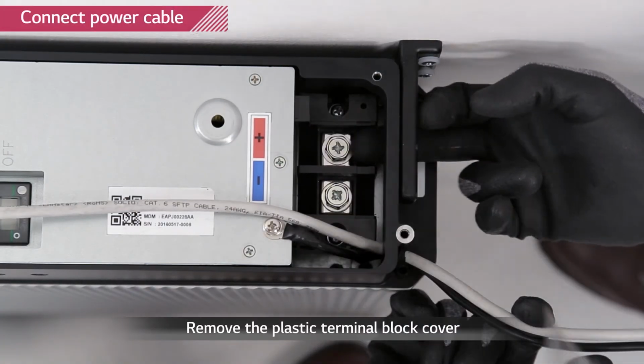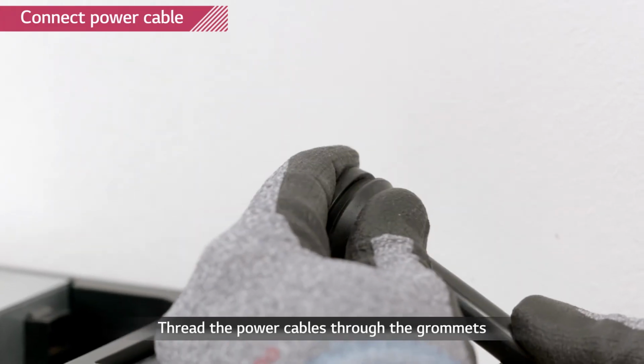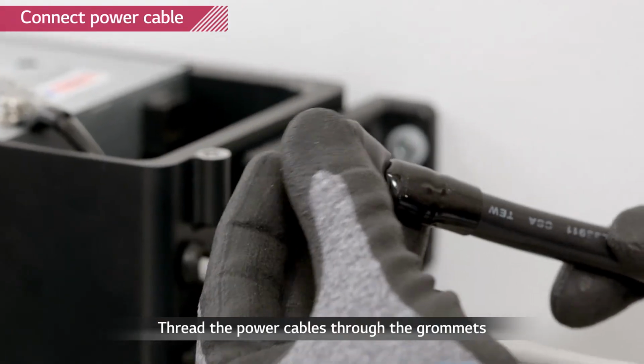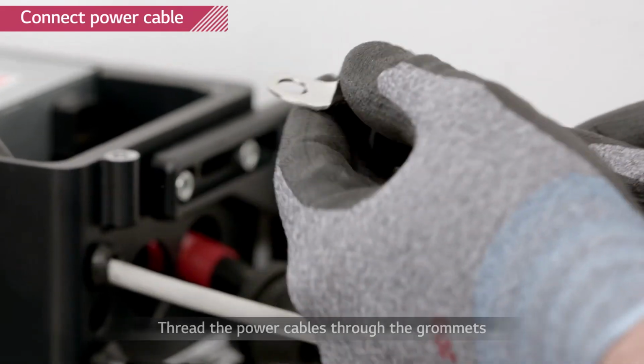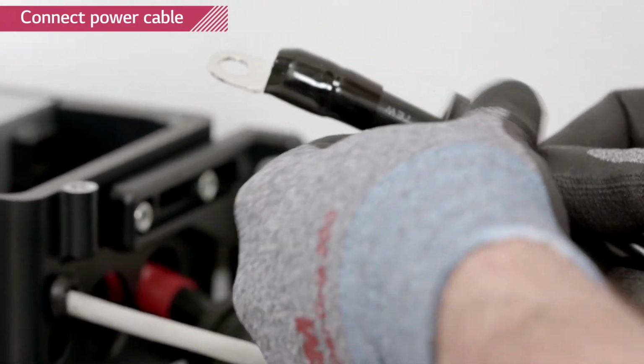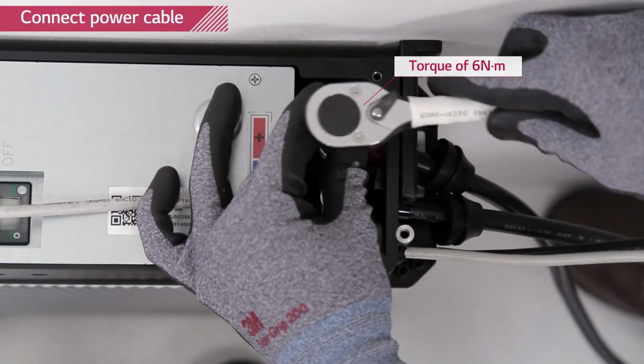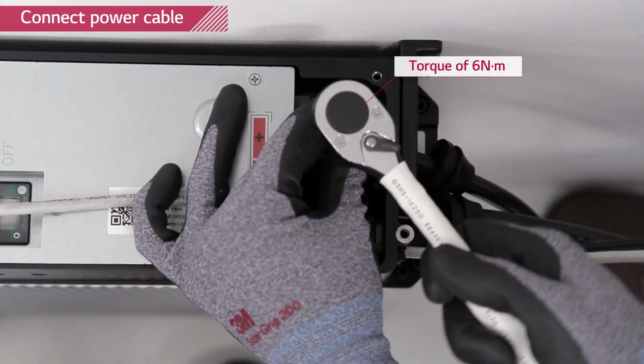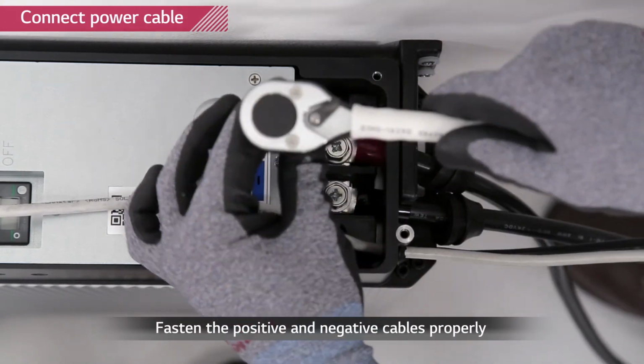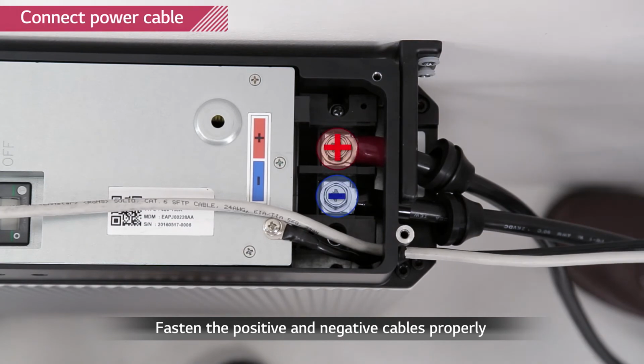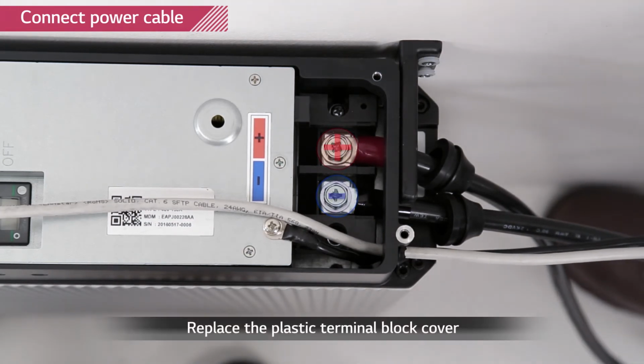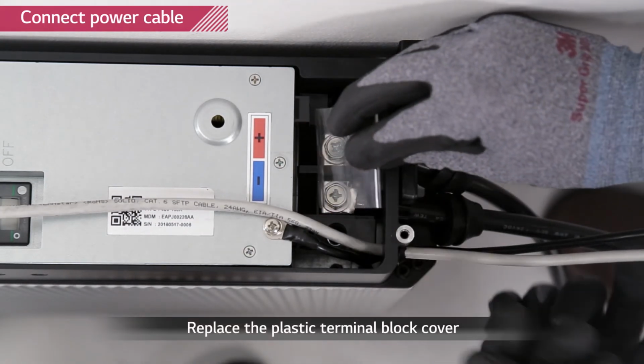Remove the plastic cover of the power terminal block. Thread the power cable through the grommet and then through the large two holes. Connect the cable to the port and tighten the screw with a torque of 6 Newton meters. Keep attention not to confuse the polarity. The right one is plus and the left one is minus, as it is marked above the terminal port.